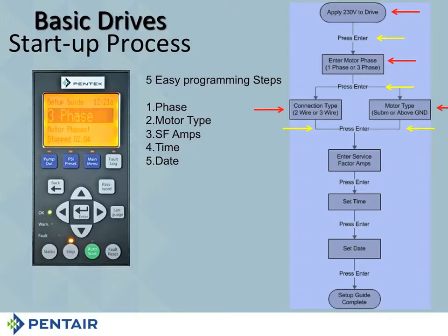Once you've pressed enter, now it's going to ask you, what are your service factor amps? Put them in and press enter. Then it's going to ask you to set the time. Now, I know a few people who want to speed the process up, so they don't want to take the time to set the time. If you don't set the time, if you just hit enter here, it accepts the default time, which is midnight. Okay? So you can just press enter and not put a time in. Of course, if you do that, you're not going to have the accurate time.